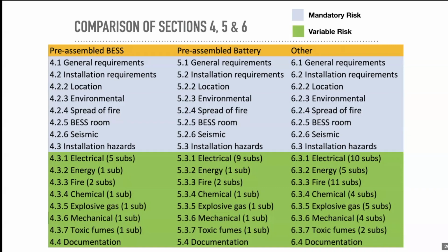So here we're again looking at that comparison table. I just want to make the point that in terms of ease of compliance, Section 4 is the easiest because it has the least subclauses. And it sort of makes sense that if the manufacturer has gone to the trouble to make their product as safe as possible, have it tested to standards, and built something that you don't modify anything on, you just basically put it in place and connect the AC and DC inputs like the PV array or the grid, then it's got a high level of safety.